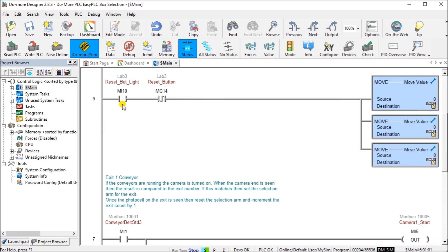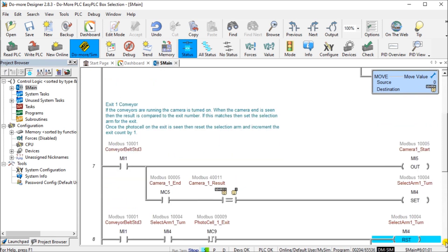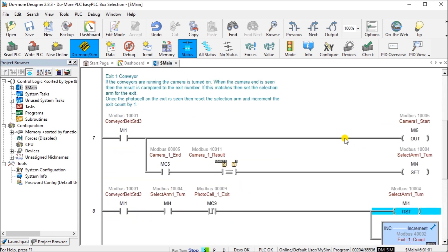For the reset button, we need to be in stop mode, door not open, emergency stop not active, and conveyor count greater than zero to output the reset button light. When the reset button light is on and we hit the reset button on the leading edge, we put zero into each of our three conveyor counters.